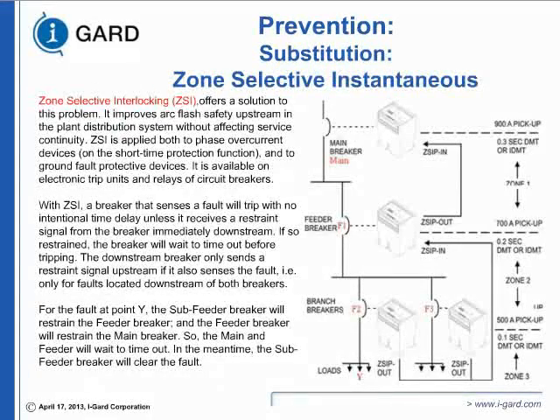You can do zone selective interlocking. Since it's very hard to coordinate all instantaneous, zone selective interlocking was a concept introduced by a very good manufacturer. That means the devices talk to each other. If the fault is downstream, that relay or protection device is telling the upstream one, I have it.